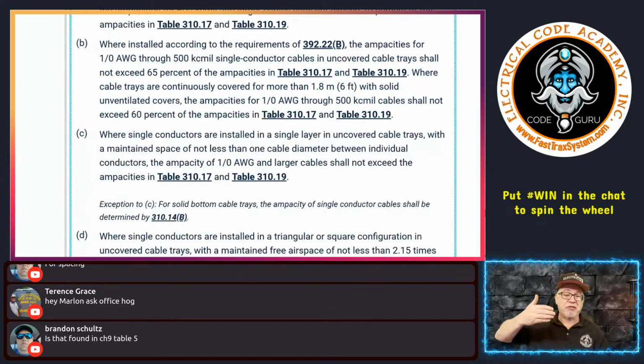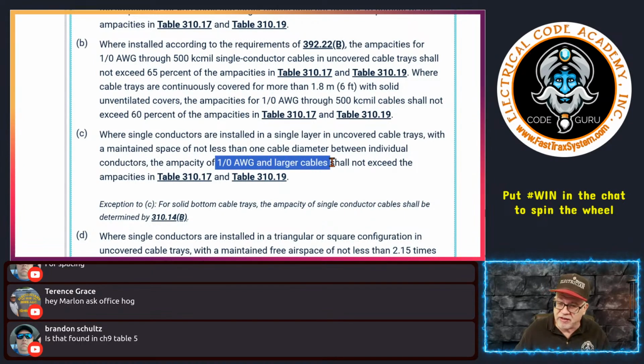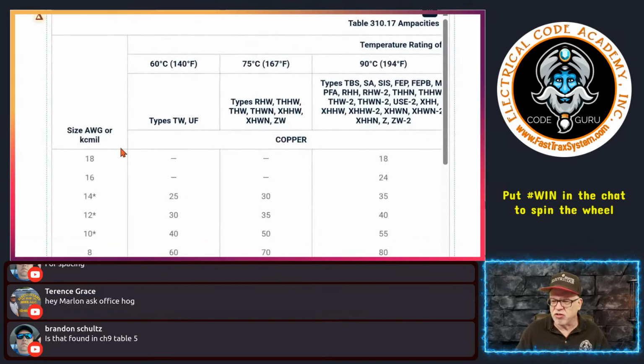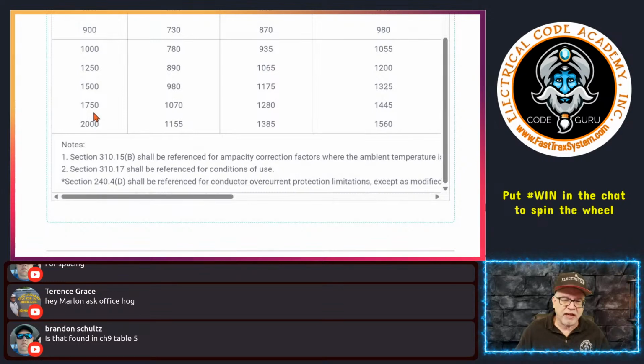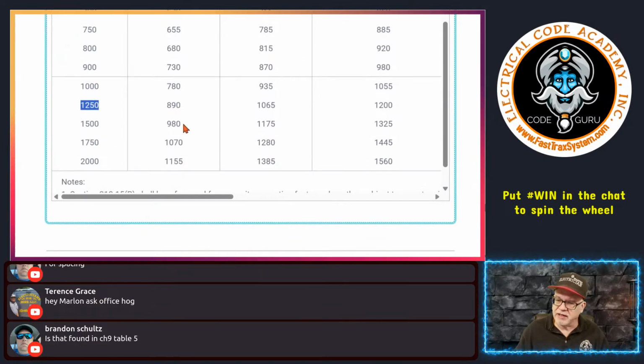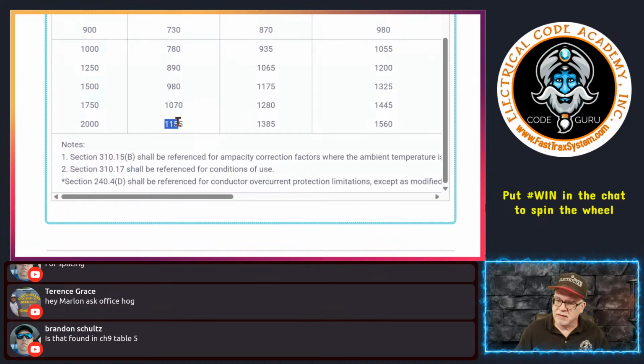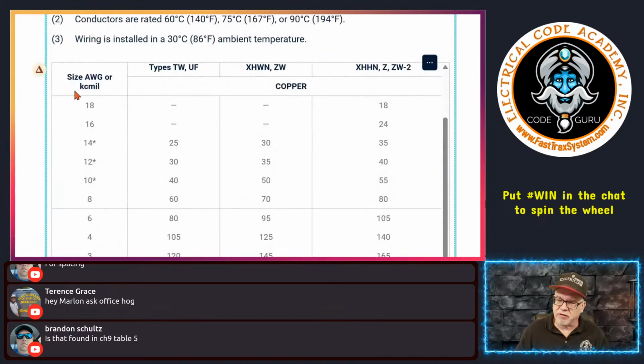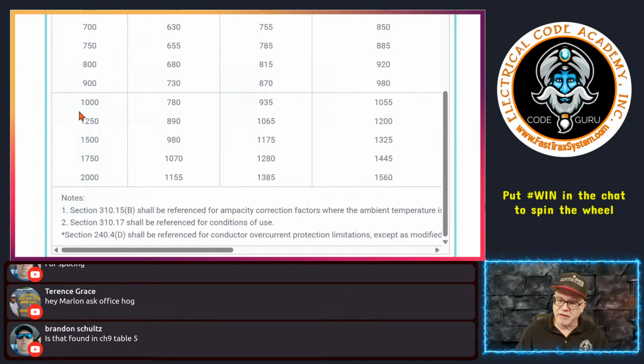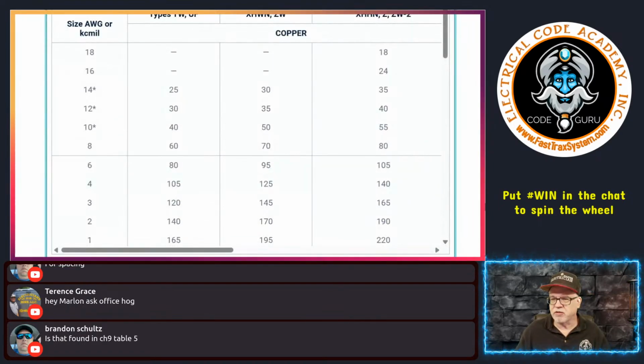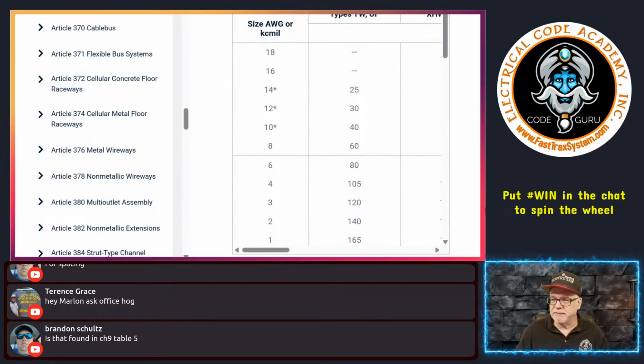When you get something outside of that table, like really large conductors in a tray, and that can apply because this says 1/0 and larger and doesn't put a ceiling on it, then if we go to 310.17, for example, I'll just show you. You see here, it goes up higher than that. The conductors right here go up higher, and down here the kcmils can go up higher: 1,250, 1,500, 1,750, 2,000. Those aren't typically given in there. So just things to keep in mind.